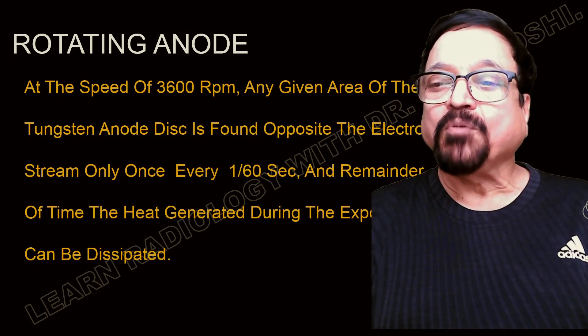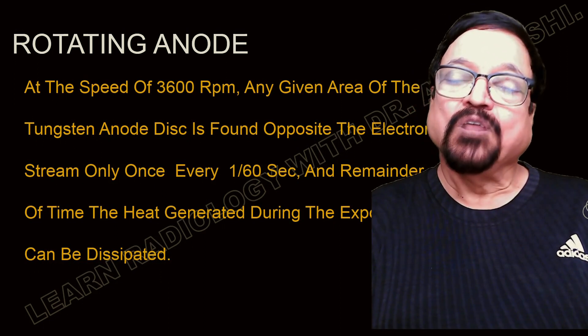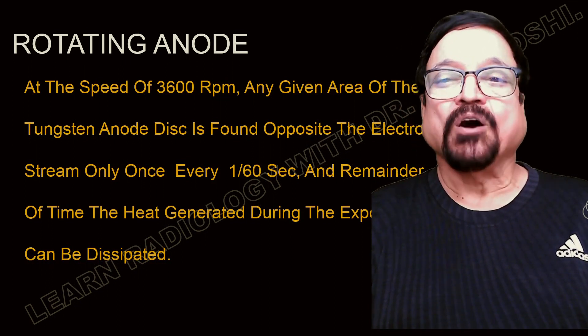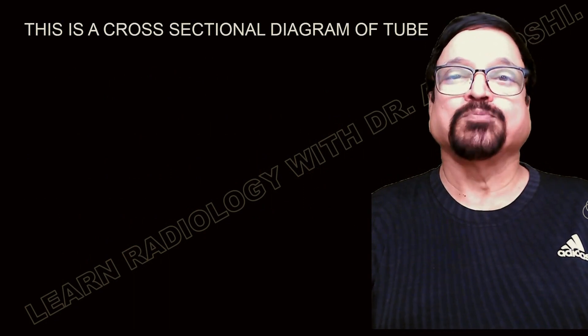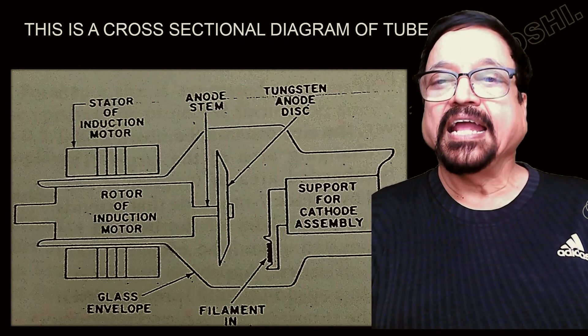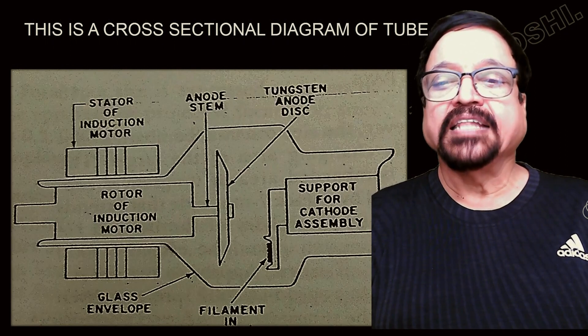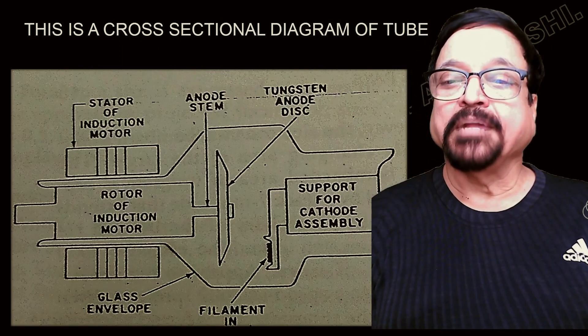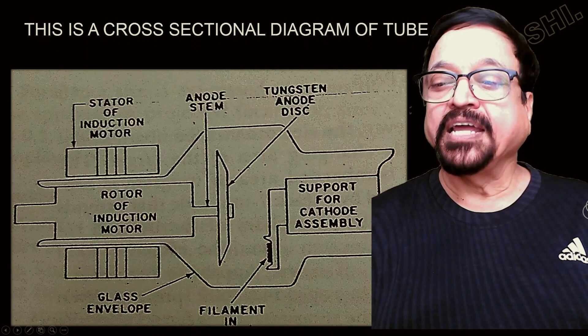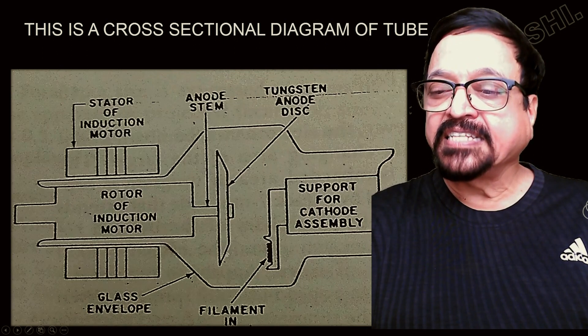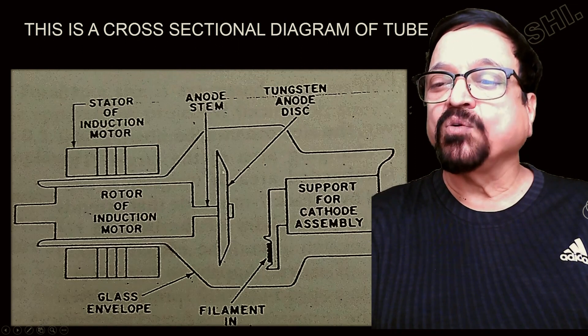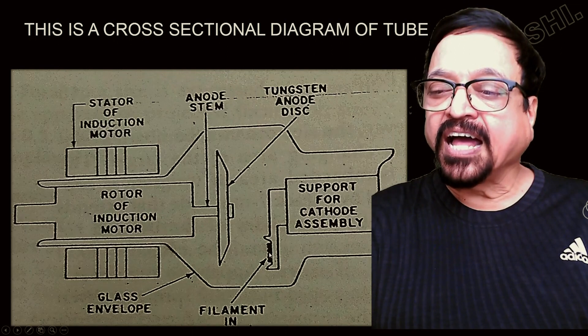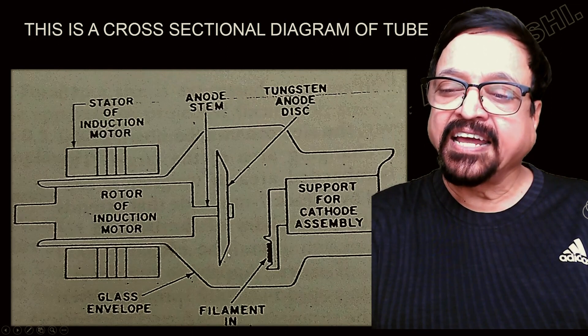Every fraction of a second the heat produced remains at that spot momentarily, and then a different surface of the anode is exposed. Looking at a cross-sectional diagram, you can see the stator of the induction motor, the rotor of the induction motor which rotates the anode at 3600 RPM, and the anode surface which is being exposed. From the cathode, electrons are produced, accelerated, and hit the anode surface — with a different surface presented each time.